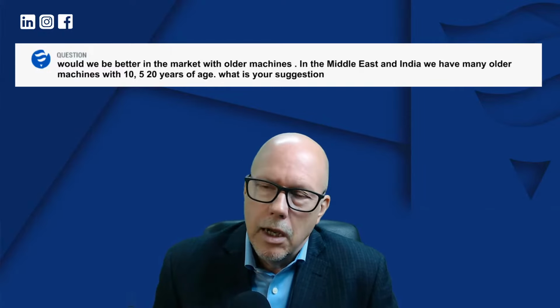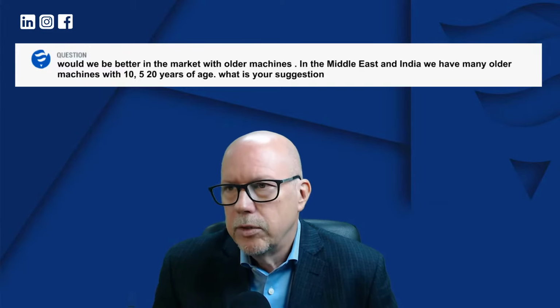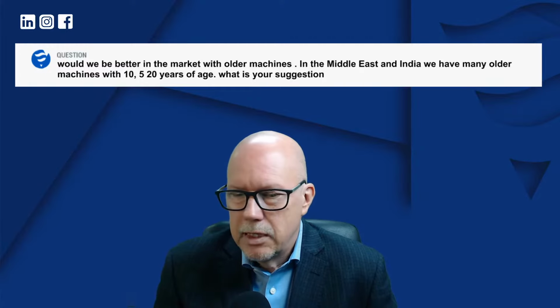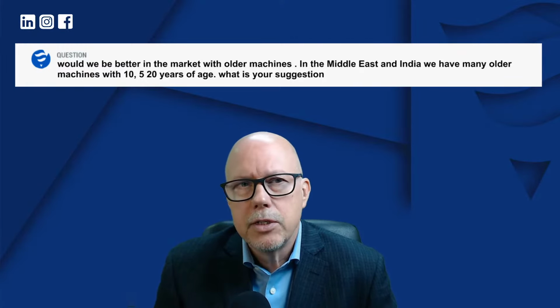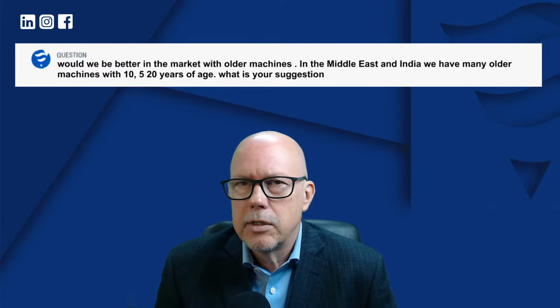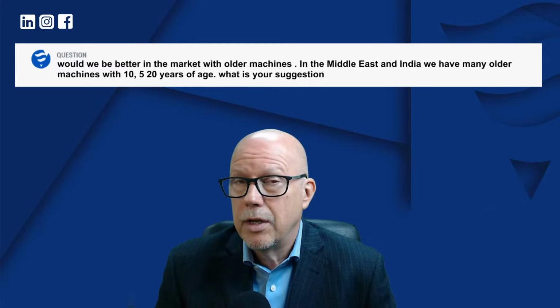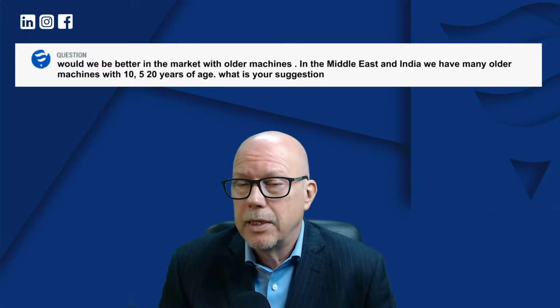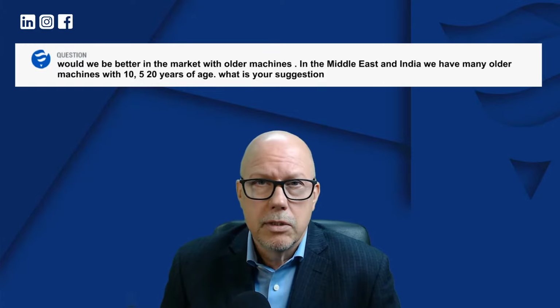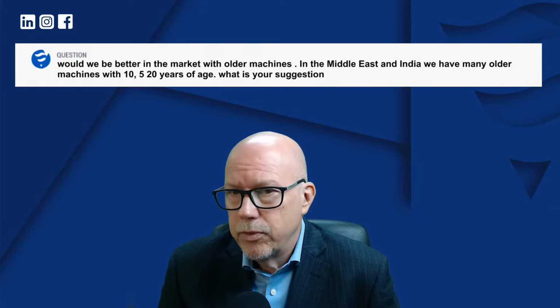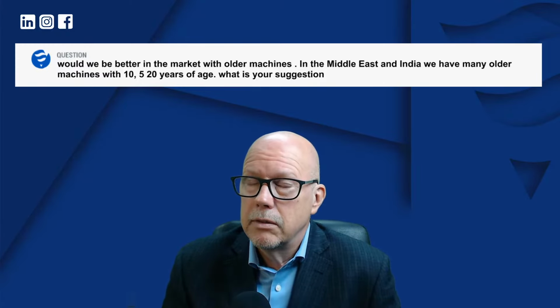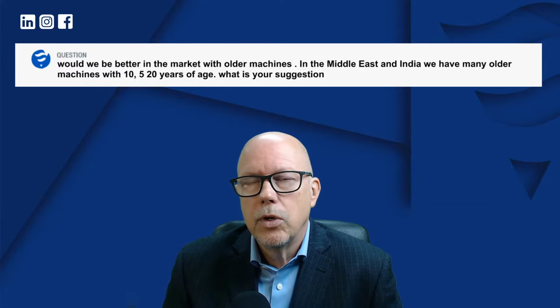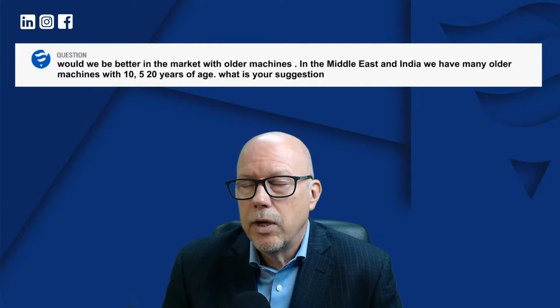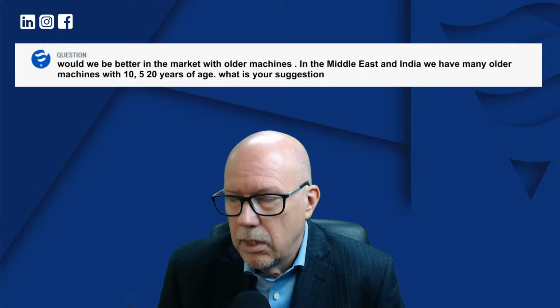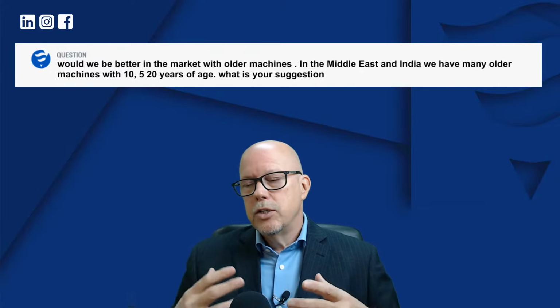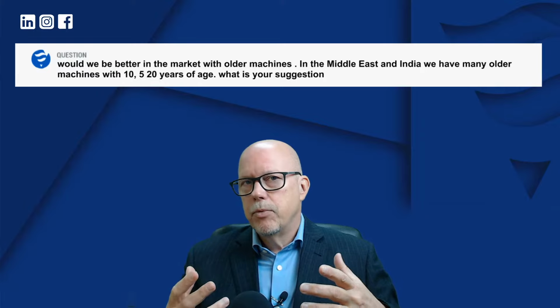Now, if you're talking about 10-year-old, 20-year-old units, as we mentioned previously in other Q&A sessions, a lot of the units that are designed for baseline operation are now called upon to operate as peak load units. So they're cycled much more frequently, and the units were not designed for that. And since the units were running for quite a few years as base loads, especially the insulation has had damage because of the operation of the unit.